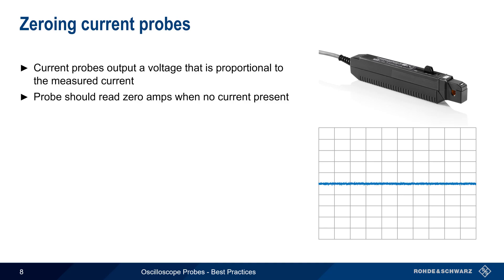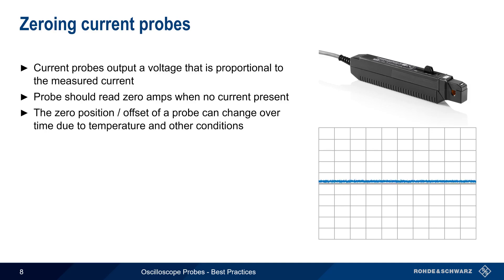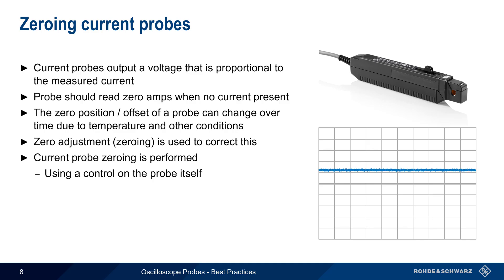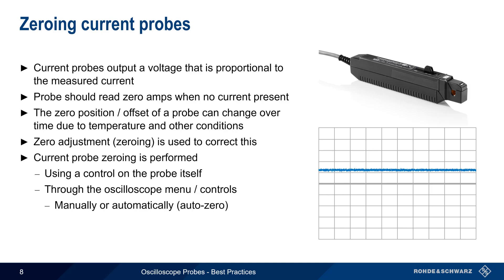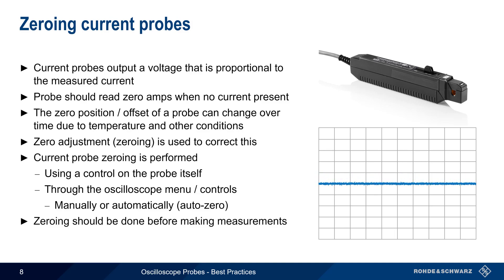Our next two tips involve current probes, which produce an output voltage that's proportional to the amount of measured current. Ideally, a current probe should show a zero ampere reading when no current is present. But due to temperature and other environmental conditions, the zero value of a current probe may change over time. This can and should be corrected using zero adjustment or zeroing. For probes with a non-proprietary interface, a zero offset knob or wheel is usually built into the probe itself. Probes with a proprietary interface usually allow zeroing to be performed using the scope menu or controls, and some scopes even have an auto zero function that applies the correct offset automatically. For best accuracy, it's always a good idea to zero current probes before making any current measurements.